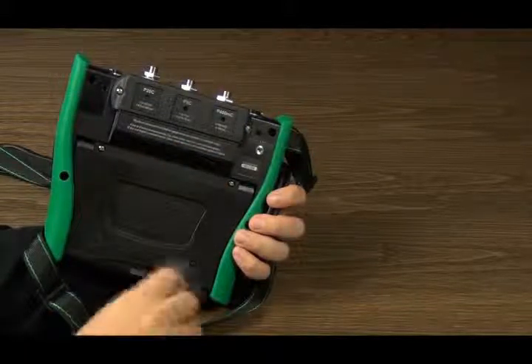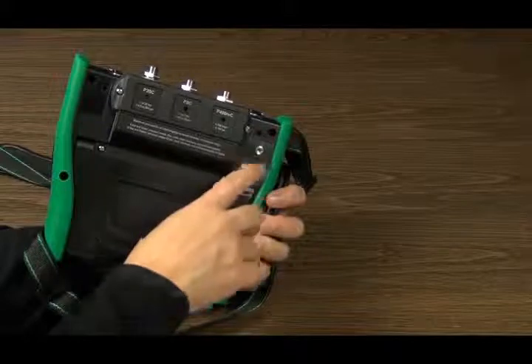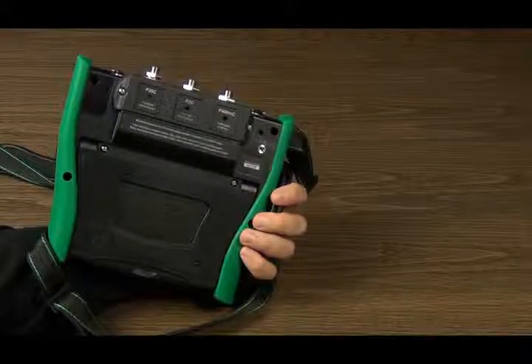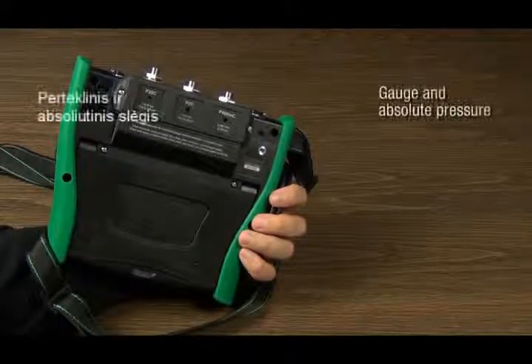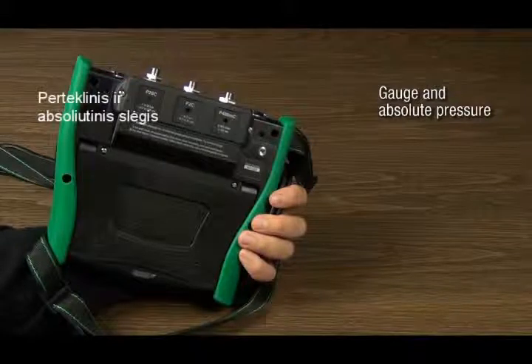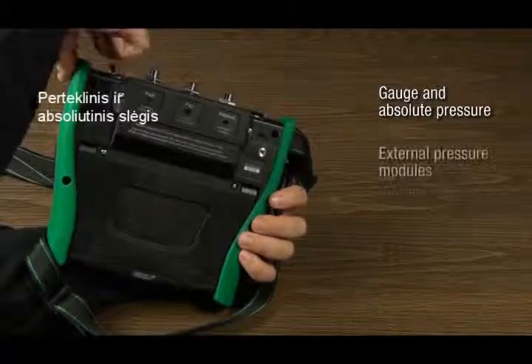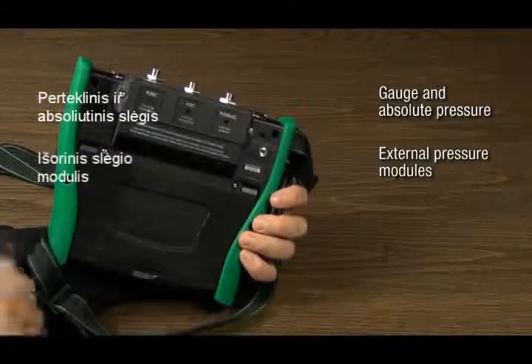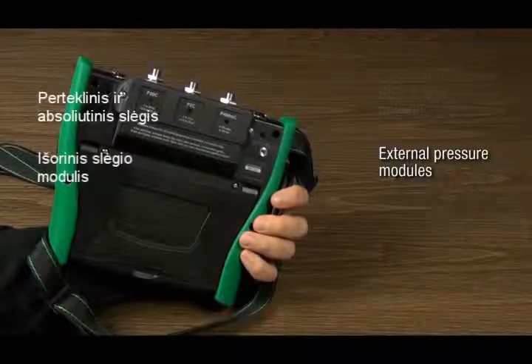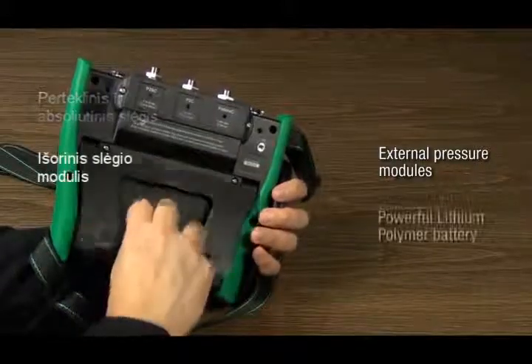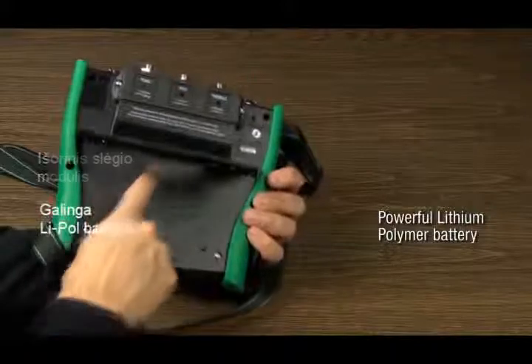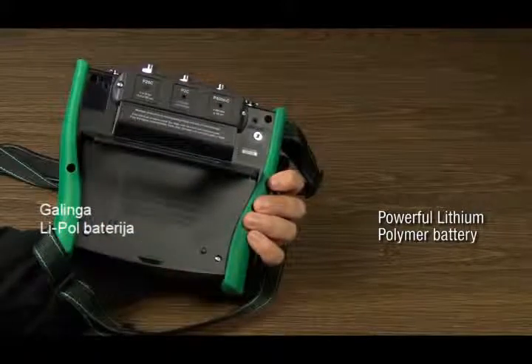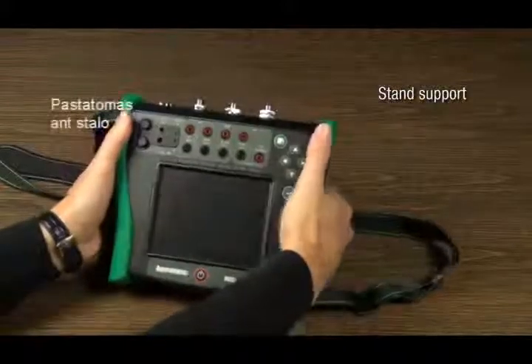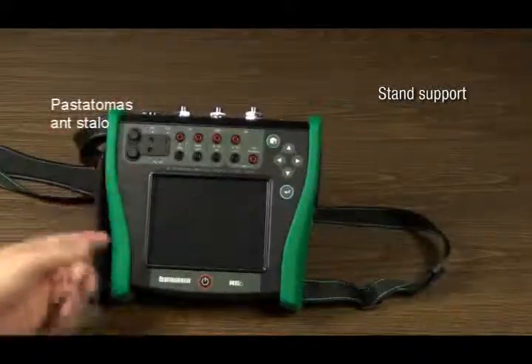The internal barometric module has a dedicated location. When the barometric module is installed, all other gauge modules can also measure absolute pressure. Also, external pressure modules can be connected to the MC6. The MC6 features a powerful modern lithium polymer battery pack, which is located here under the cover in the rear panel. The stand support sets the calibrator in optimum position in tabletop usage.